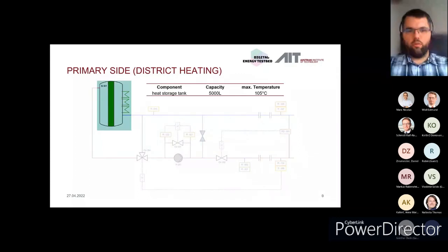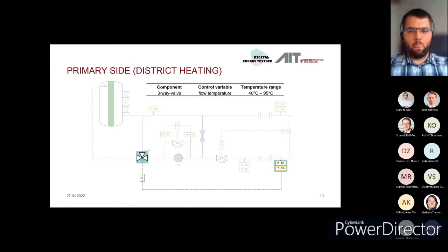First, our heat storage tank with a capacity of 5,000 liters, as Thomas mentioned, with a maximum temperature of about 105 degrees Celsius. It depends on how much energy we need, so we could raise or lower it a bit so the losses are less than at 105 degrees. This stored water is then mixed by the three-way valve with the return temperature from the district heating substation, so that we reach a flow temperature at the inlet of the substation.